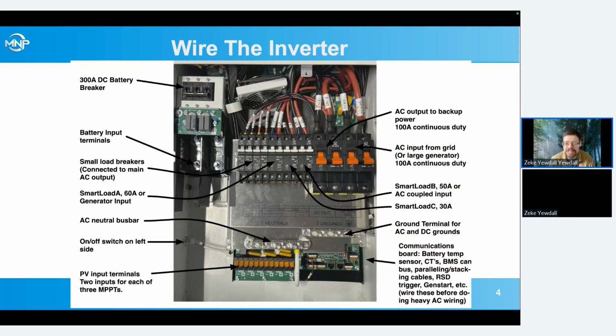Here's kind of a view of the inside of the inverter. We've got our battery breaker and our battery input on the left, our main 100 amp AC input and output on the right, and then all of our smart loads and additional load breakers. And down on the lower left, we've got our PV inputs, 2 input terminals for each of 3 different MPPTs, and then our neutral and our ground bus bars for our AC, and then all of our communications boards.